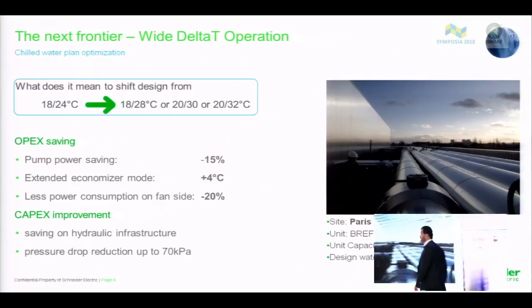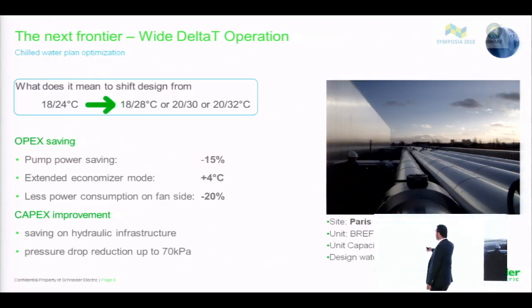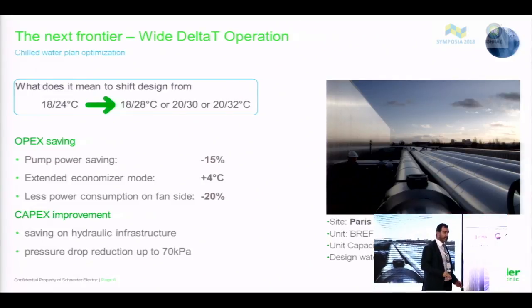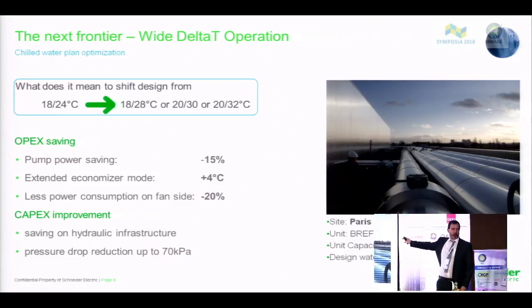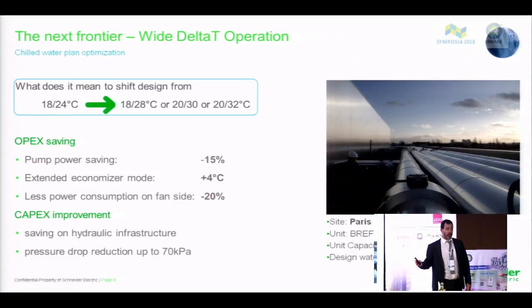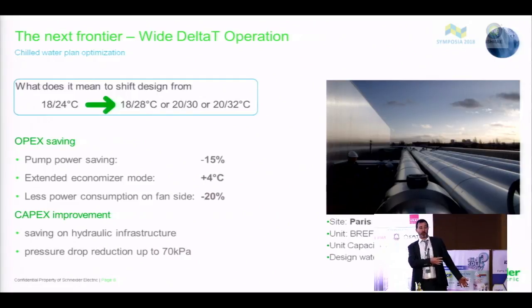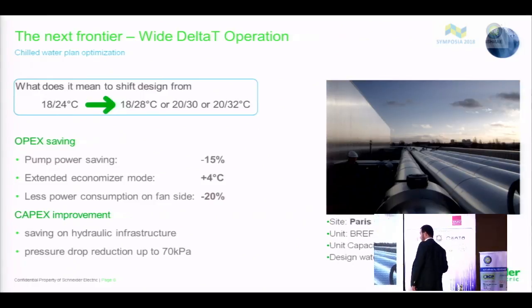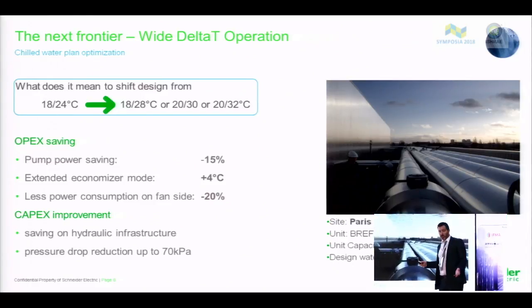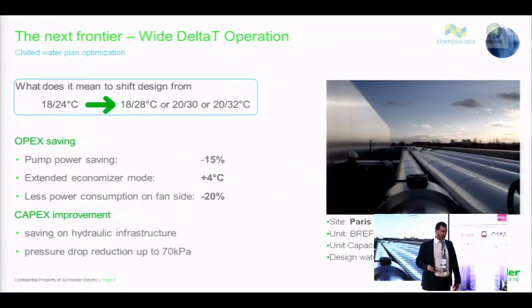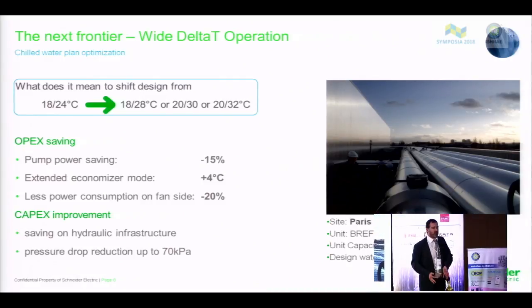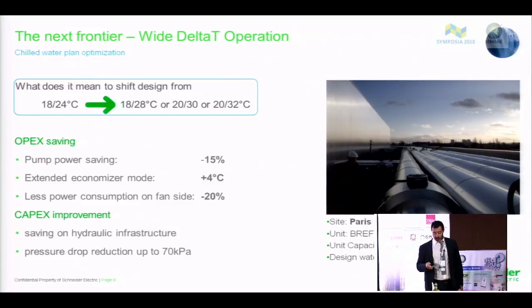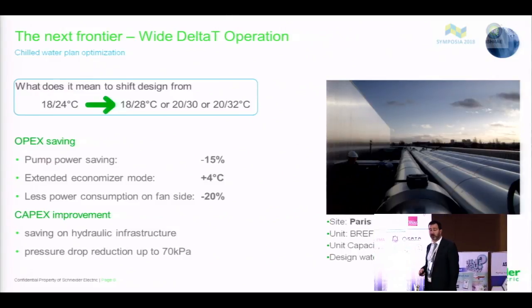It changed completely the scenario because we are able to increase the inlet water temperature. And it is just a design view, not something magic on the unit. The unit should be designed properly, of course, but it is a design choice based on the recommendation of ASHRAE. We are not reinventing the wheel. We are just applying what ASHRAE is saying. Of course, knowing that it is necessary to have a unit that is able to do this. Not all the chillers are able to do this, but the mission-critical chillers are able to do this.